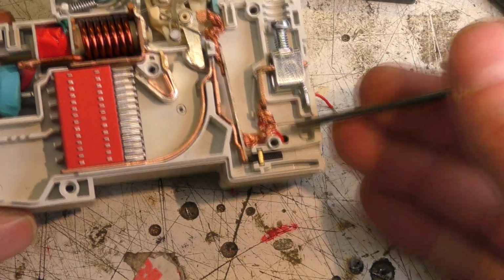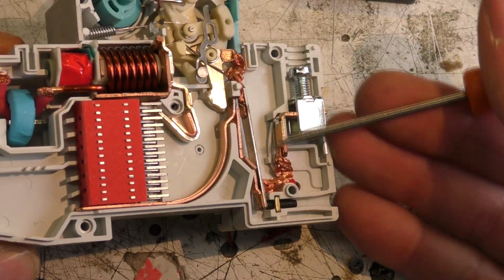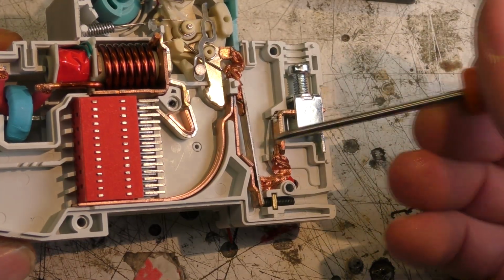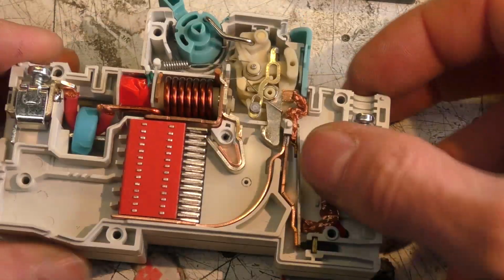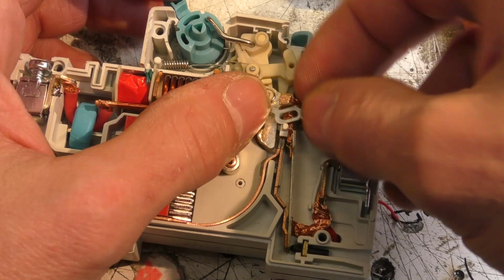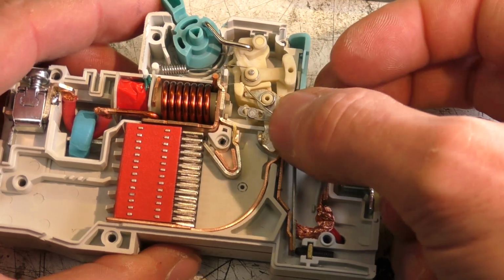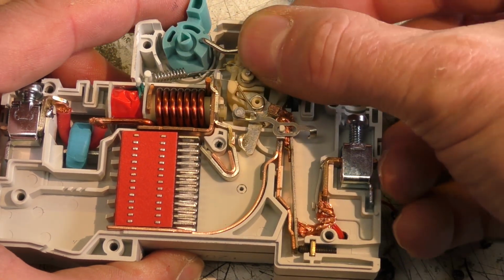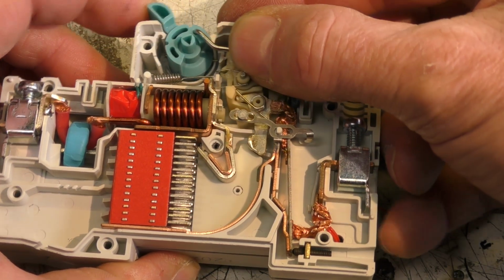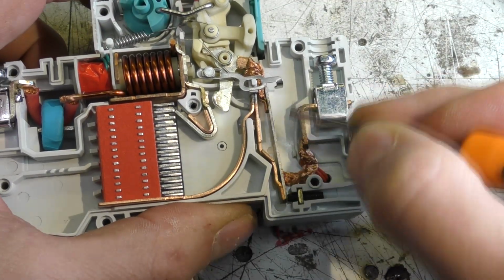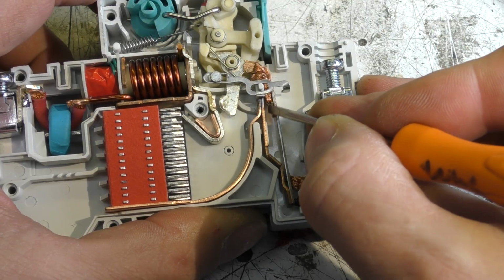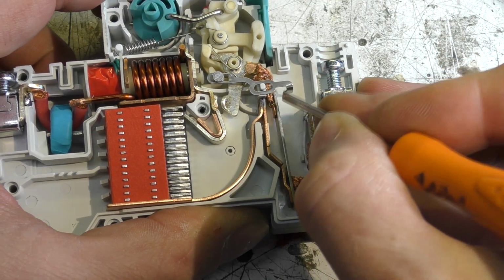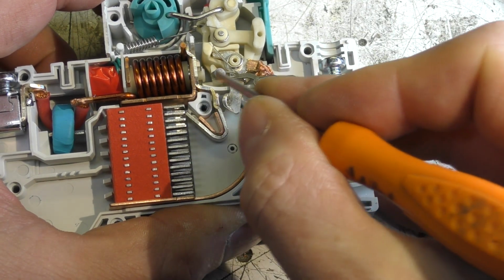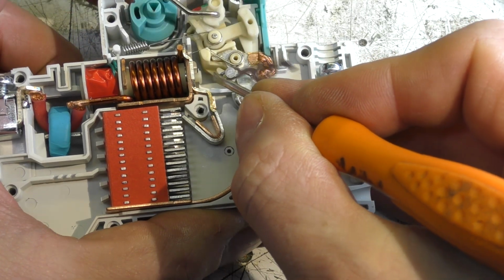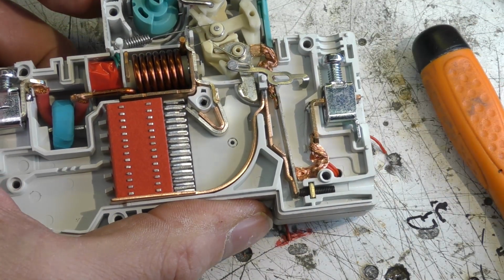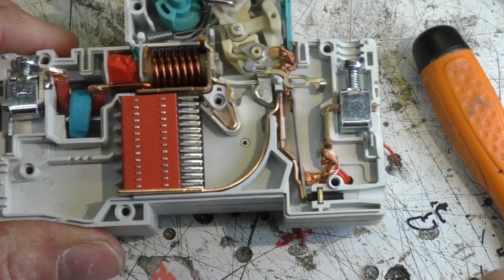Over this side we've got these two wires that just go either side of this piece of copper, so this is clearly being used as a current shunt. And the rest of this looks like the normal sort of fairly convoluted mechanical arrangement for a conventional circuit breaker. So this is the bimetallic strip that does the thermal part of it. As it heats up it starts bending in this direction, hits this lever, which I think then pulls that to trip it thermally, so for a longer term overload.